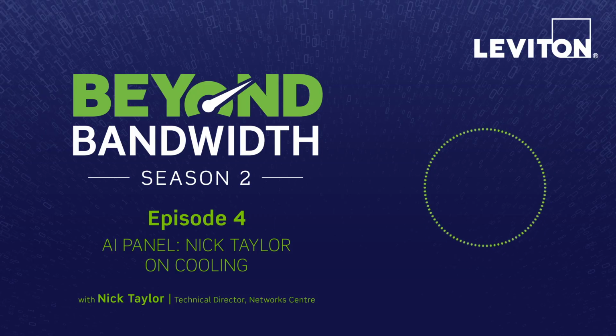So just a little bit of background. Before air containment, I'm sure many people in this room probably remember it. I was talking with a colleague earlier about an air traffic control site where there were about 100 racks in there, and they were all facing the same direction. And obviously, as you got further down the room, the heat got greater and greater. But the kind of general model was that you'd have rows of racks. They'd be set into aisles of 2 rows, backs of racks facing backs, fronts to fronts. You'd have a raised floor. You'd have perforated tiles in the floor. The cold air would be sent from the perimeter air handling units under the floor to the front of the racks, hot air out the back, and return to the units.